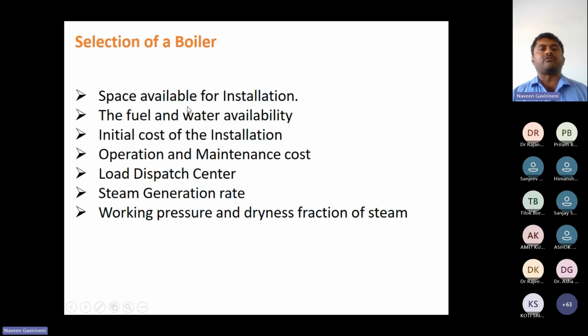So, selection of the boiler. How can we select the boiler? These are the factors: space availability, fuel and water availability, initial cost of installation, operation and maintenance, and load dispatch center. Suppose the load dispatch center, SLDC, is not nearby. We will again have to spend money for more and higher transmission lines from the department. Then steam generation rate and working pressure.